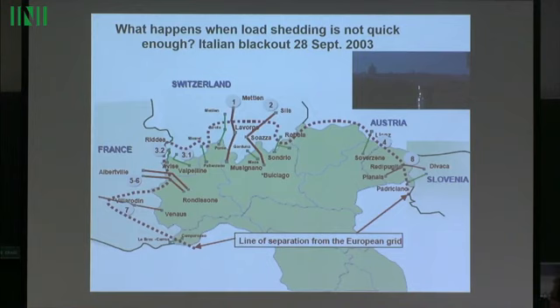So when that line tripped, it overloaded the second line, which also tripped, and then all the lines connecting Italy with the rest of Europe tripped one after another - a typical cascading blackout. So basically Italy became an isolated electrical island from the rest of Europe. Italy is an importer of power - as I said, they voted twice against nuclear and didn't build enough power stations, so they import a lot of power, mostly from France and Germany.